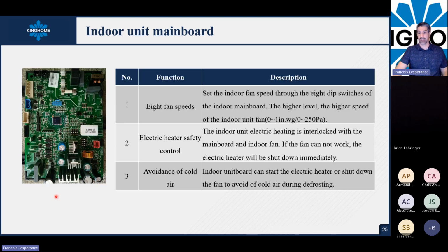For the indoor air handler, again, 8 fan speed selection. You can change the electric heater safety, and you can manage if you want to avoid the cold air during the defrost signal. So you can shut off the blower during defrost with the air handler to prevent this cold draft.